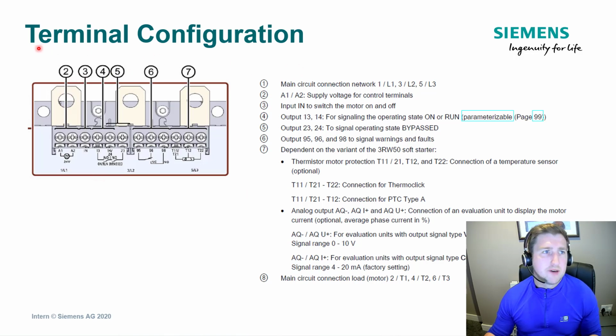So the terminal configuration here, as you can see, number 2 is the control circuit A1 and A2. Number 3 is the IN signal. So to start the 3RW50, the A1 and the A2 terminals have to be on, and also this IN signal has to be activated as well. So without either of those two, you wouldn't get a start. Number 13, 14 and 23, these are signaling contacts for how the device is running. You have an on and run signal, but you also have a bypass signal as well, which you can connect in. So just two different methods of signaling there.